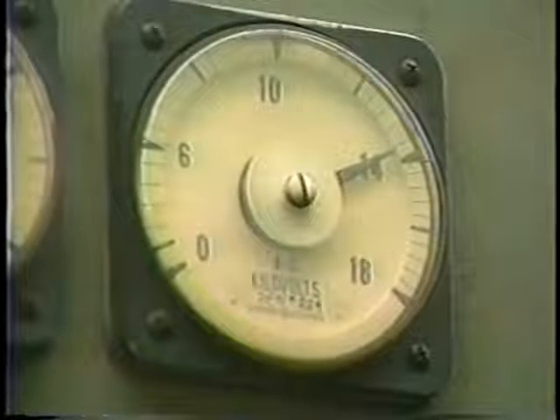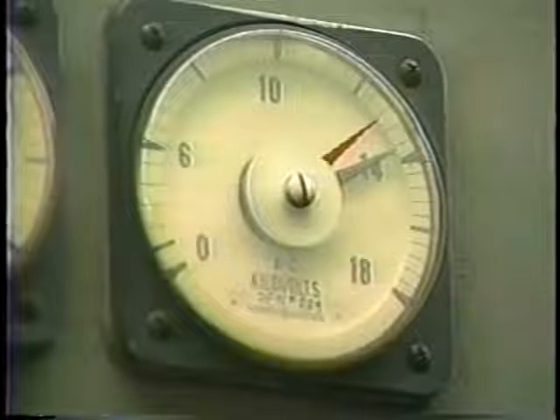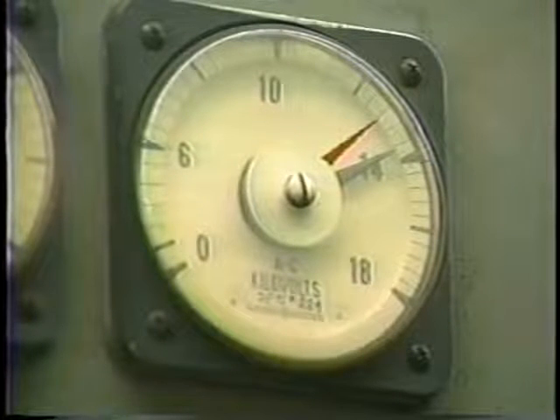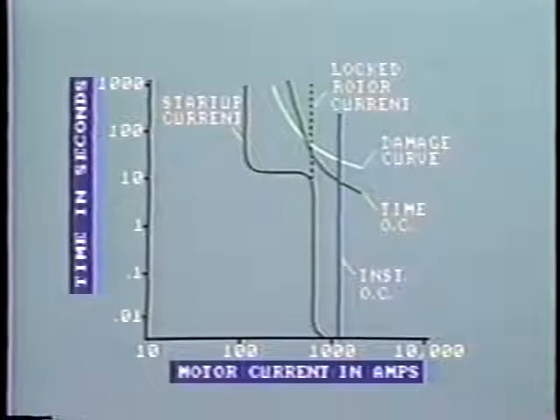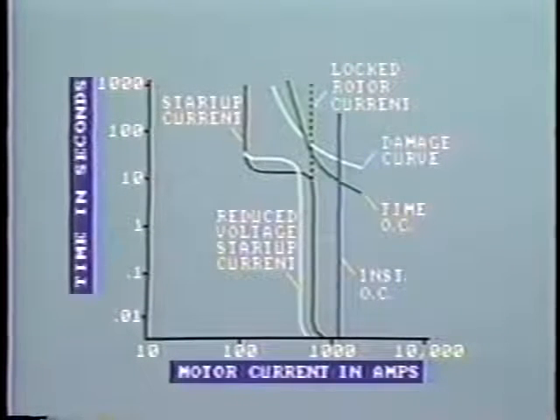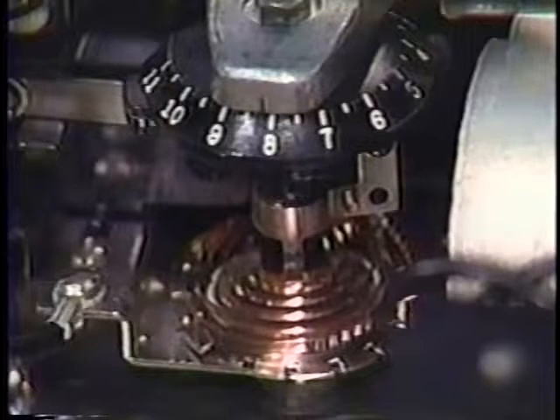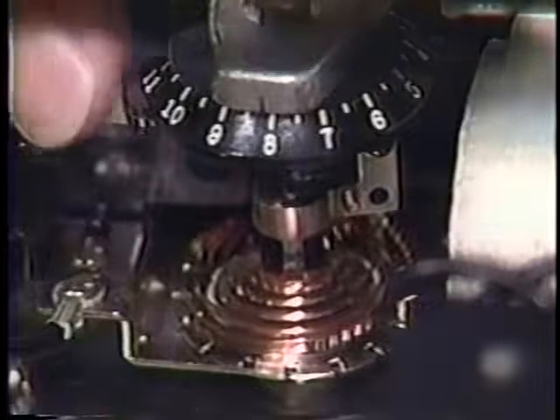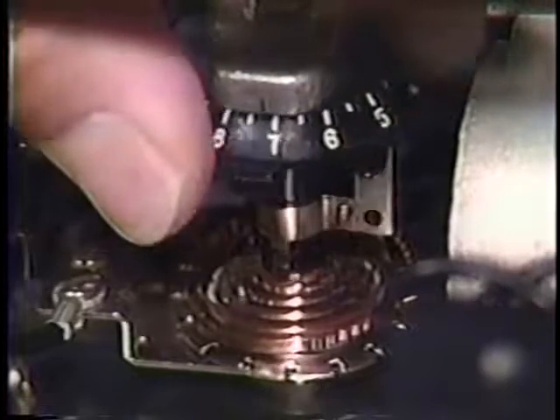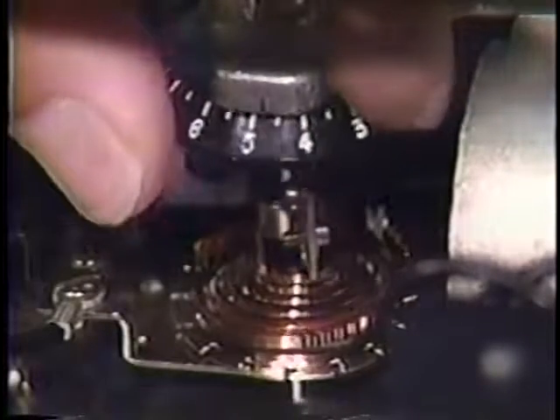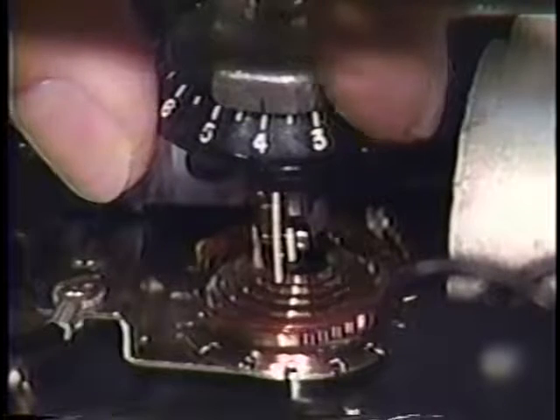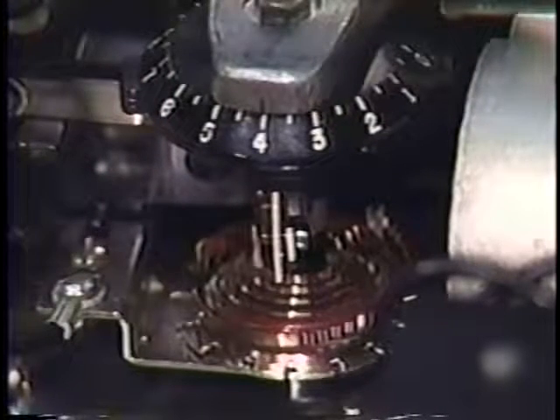Indeed, switching in a large motor may well cause the supply voltage to dip in certain installations. Under these circumstances, shown by this curve, the motor would take longer to start, perhaps 18 to 20 seconds. But as a compensation, the startup current and locked rotor current are lower. Obviously, considerable care must be taken in setting these relays so as to avoid inadvertent tripping during startup, but at the same time provide adequate protection against motor damage.